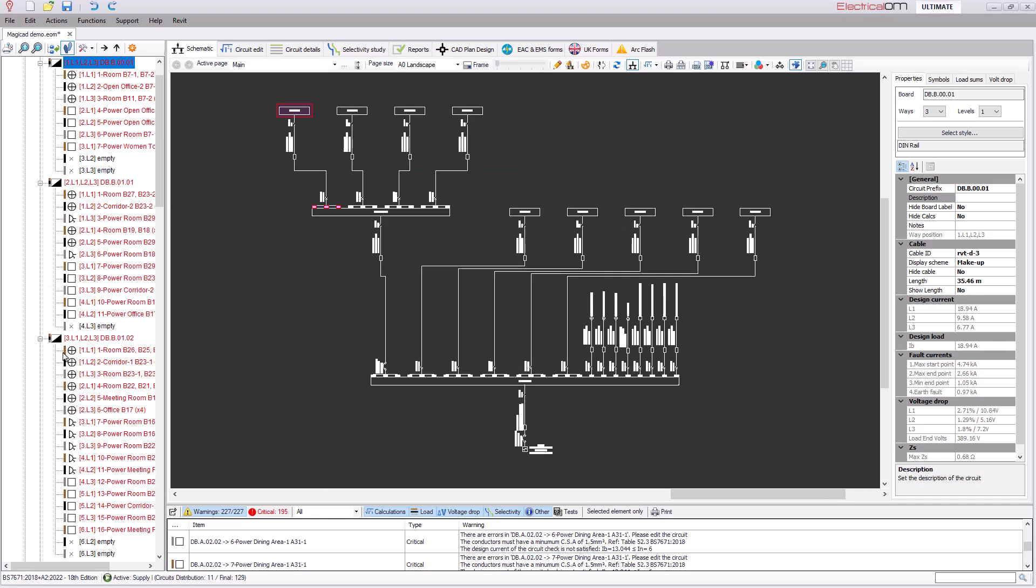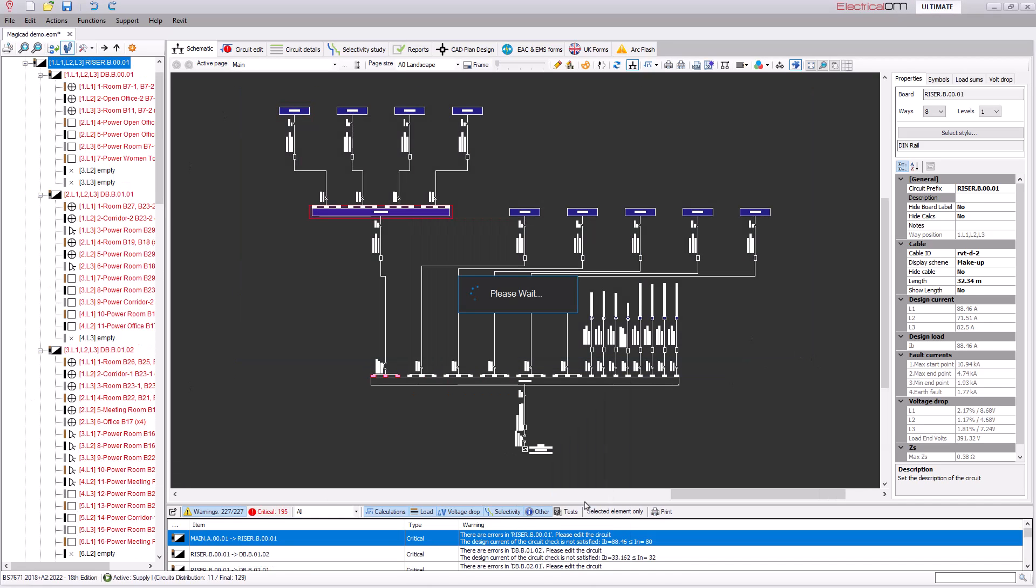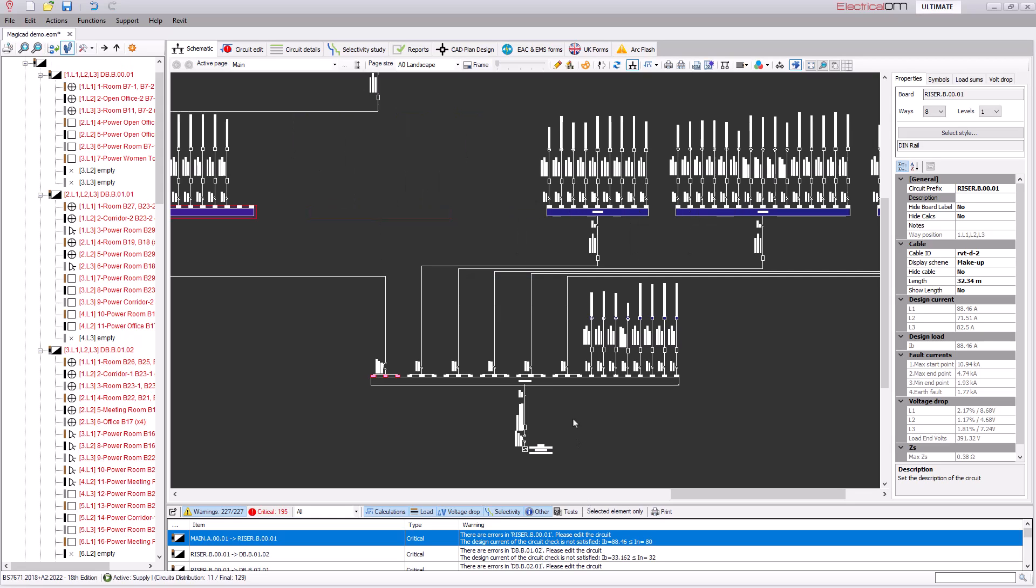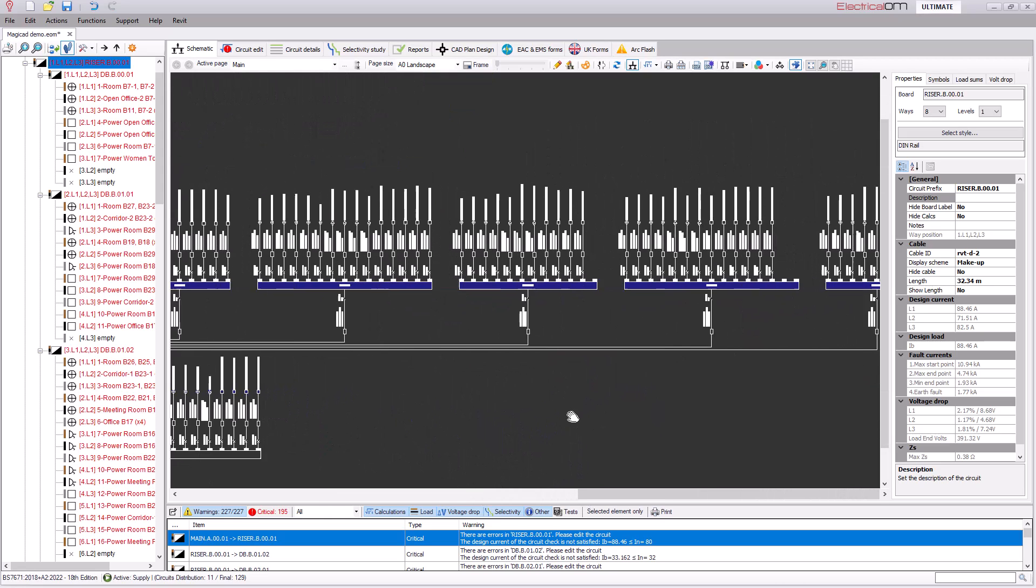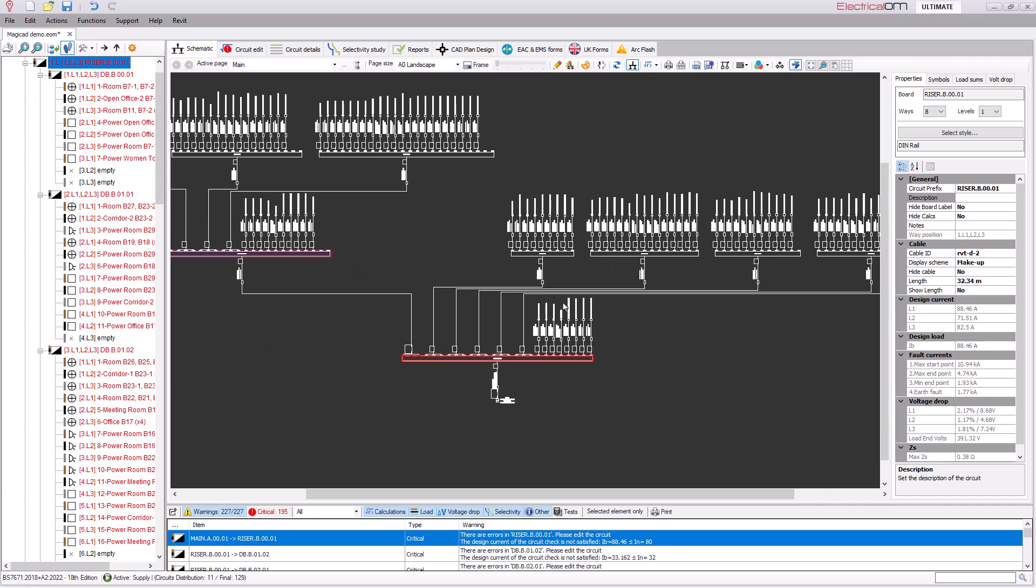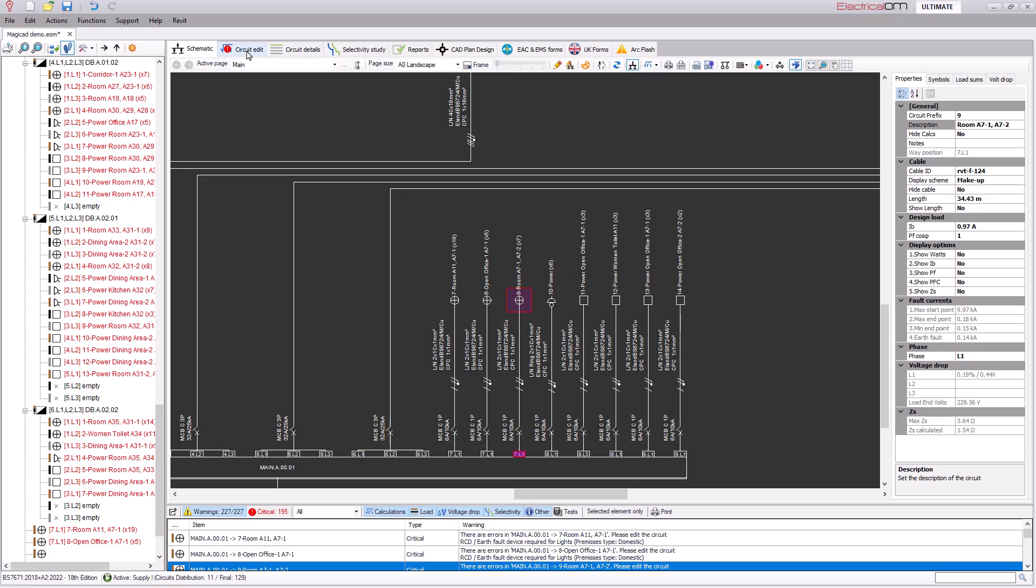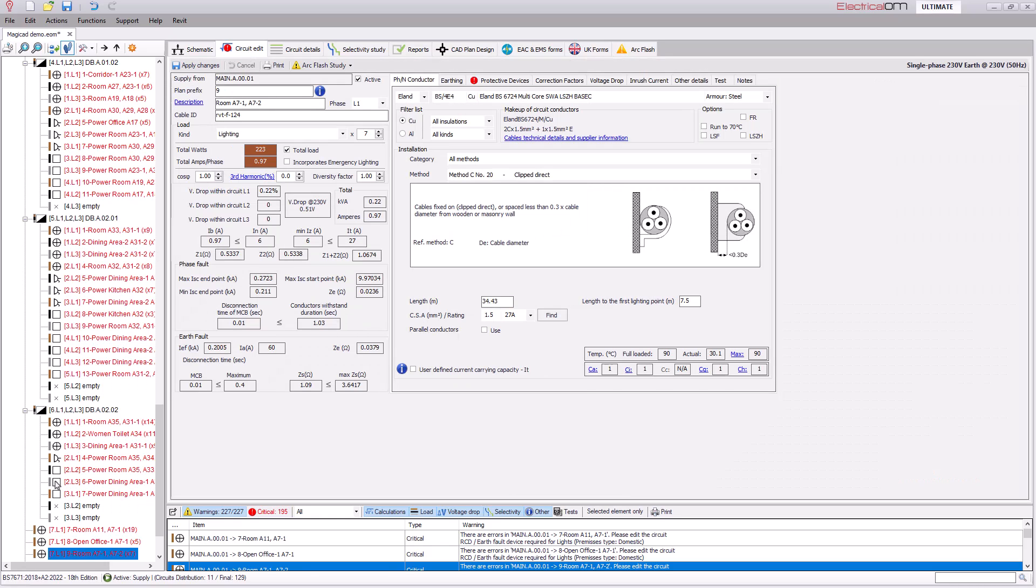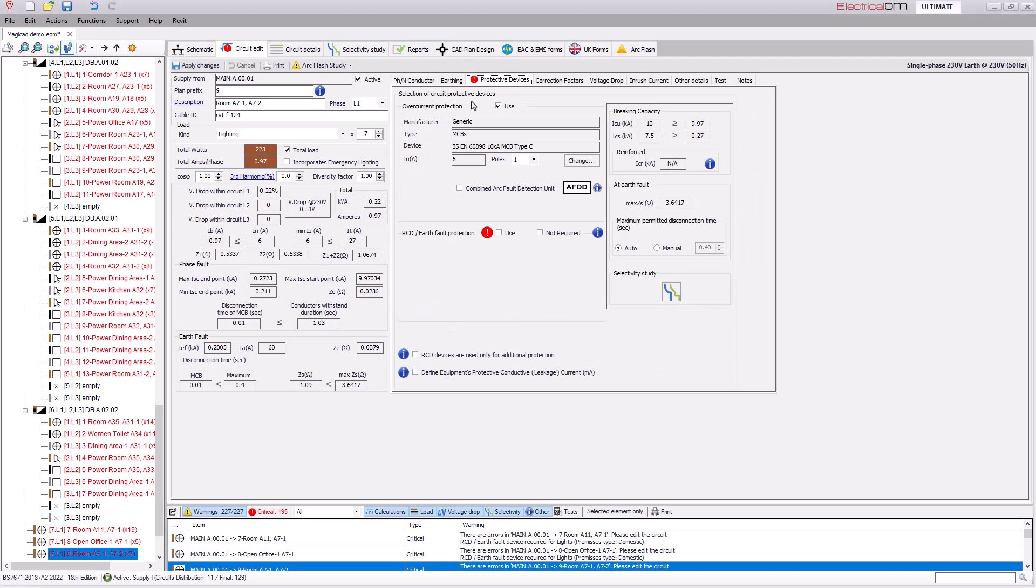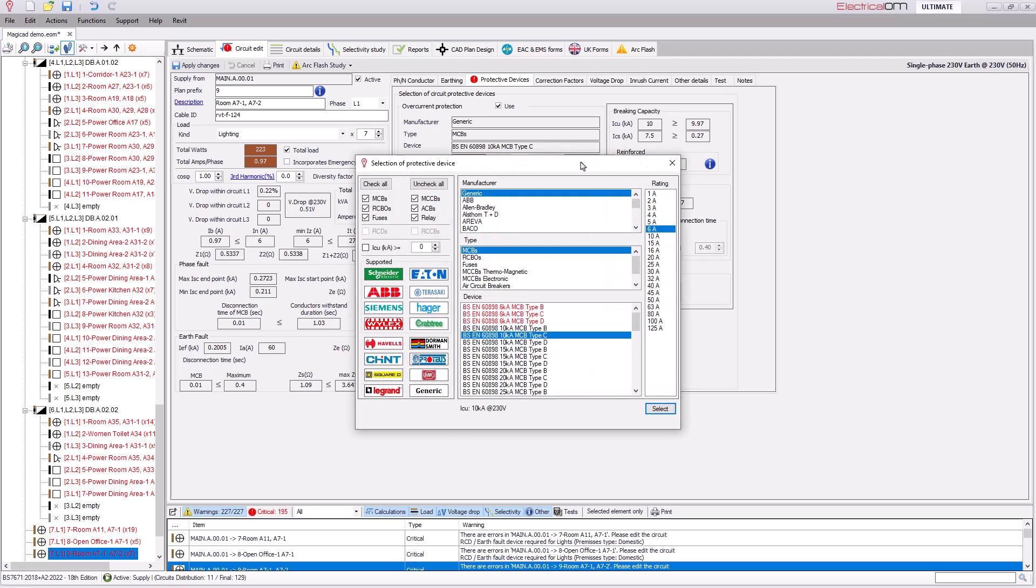Now let's take a closer look at how we can set the properties for running the calculation for our final circuits. Let's do this by taking a look at an individual circuit. In this example I will select the new lighting circuits that have been brought in from the MagiCAD model. Here I'm going to go to the protective devices where we can see a red warning markers that appear here that have an issue where we have requirements for an RCD to be installed in order for it to comply with BS7671.